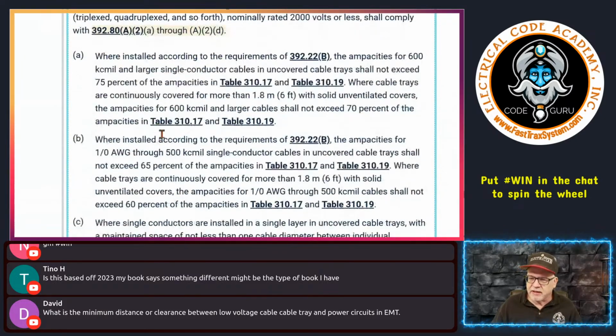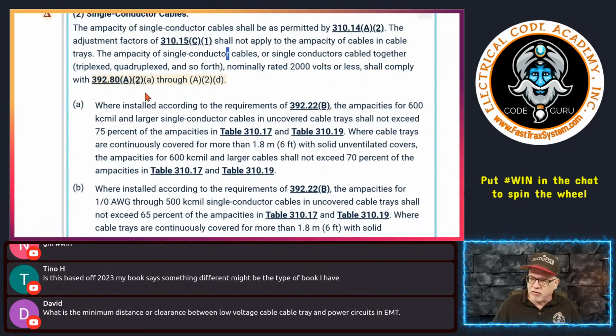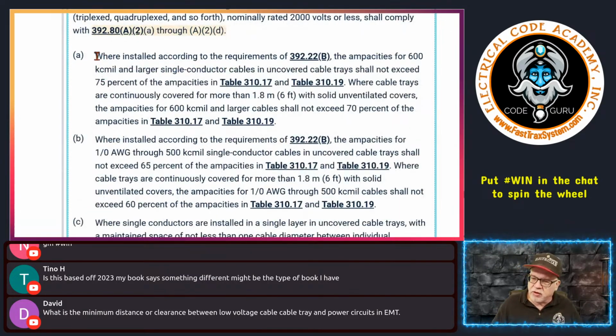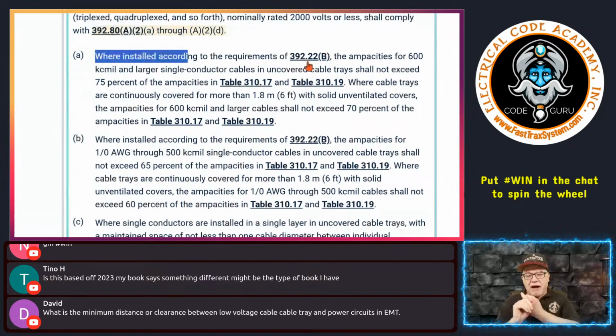Now let's look at the ampacities. Why is that? Because we're going to have other requirements that are going to reduce the ampacities of the conductors anyway. So let's look at the first one. It says they're installed in accordance with the requirements of 392.22(B). Remember, 392.22(B) was the rules for the conductors inside of the cable tray. We talked about this in part 1 of this series. I'm not going to reiterate that because I'm already over an hour, so go back and watch part 1.